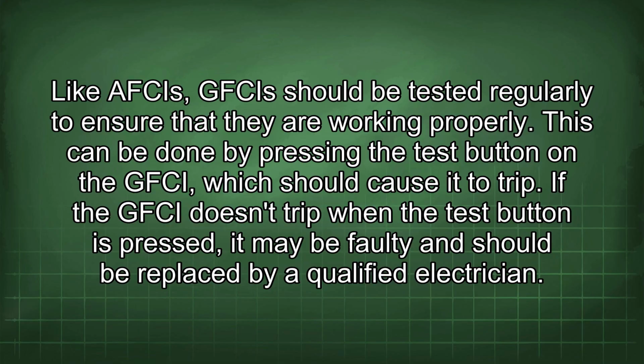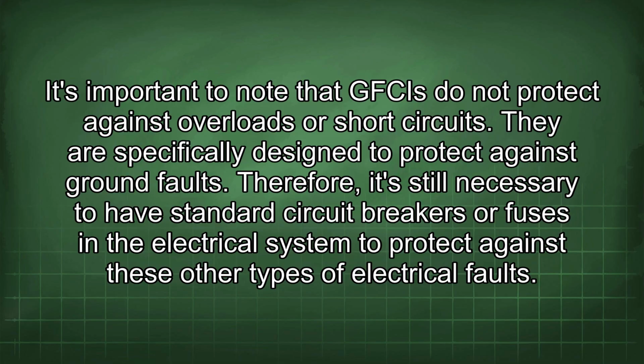If the GFCI doesn't trip when the test button is pressed, it may be faulty and should be replaced by a qualified electrician. It's important to note that GFCIs do not protect against overload or short circuits. They are specifically designed to protect against ground faults.